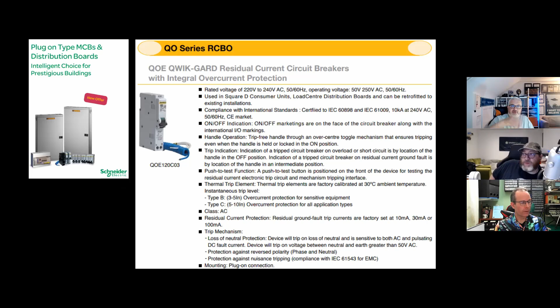There are two categories of RCD mentioned in the Schneider document. In the event of a loss of supply required to address the fault and trip, there are two categories of behavior. Category 1, the RCD does not open and continuity of service is optimum because the load is powered on when the voltage is restored. So that to me is like latching, non-latching, etc. But the RCD is unable to operate if the loss of power supply is a result of a neutral break. The presence of line voltage is a hazard because the RCD is no longer able to perform its protective function in the event of contact with the line potential.